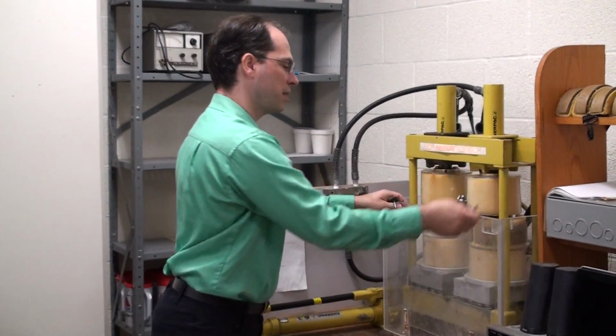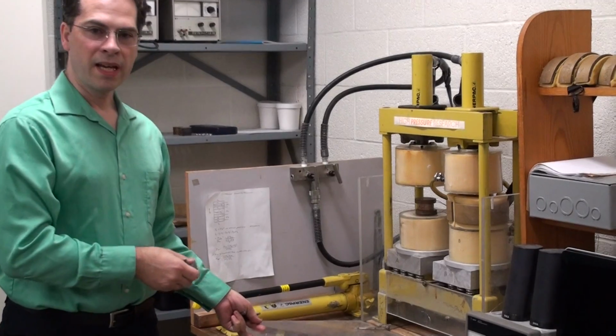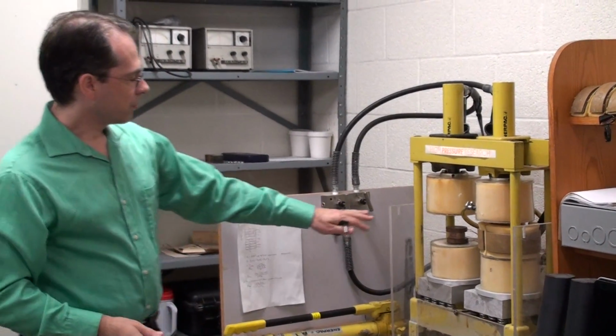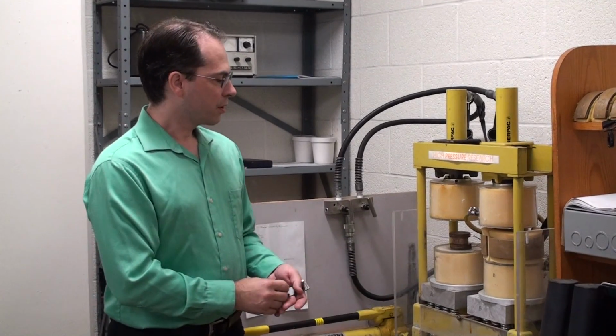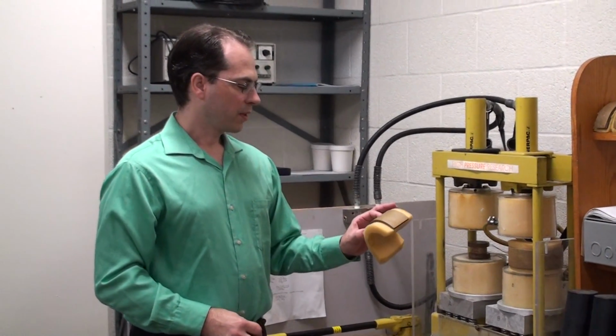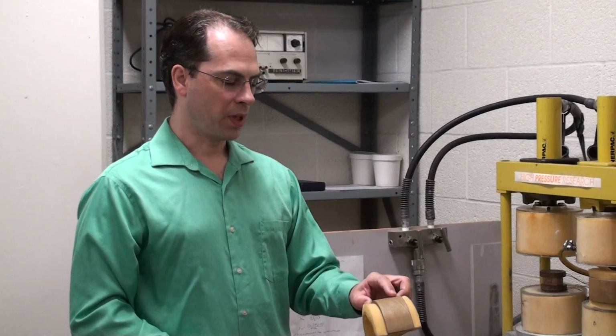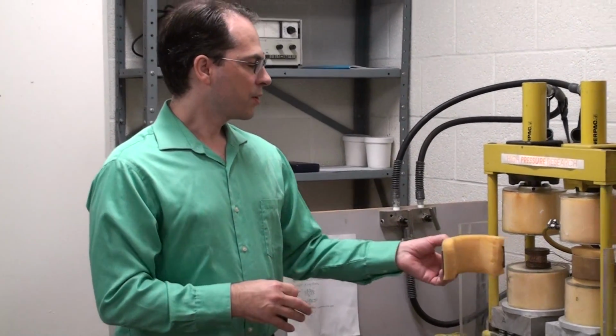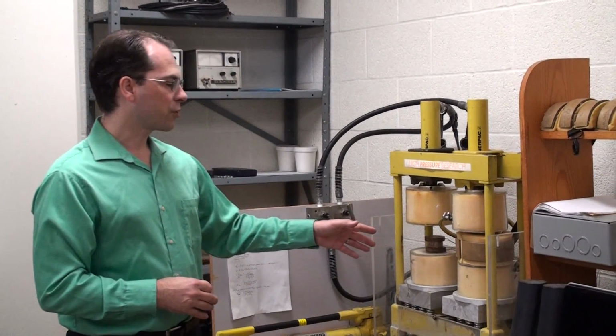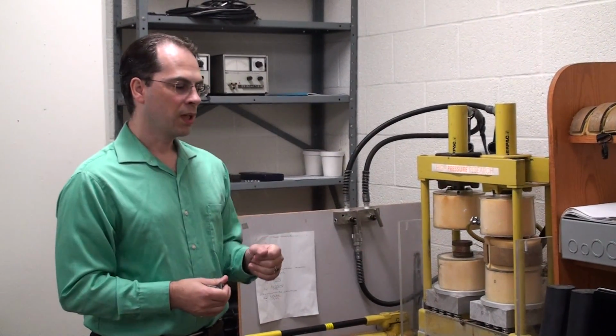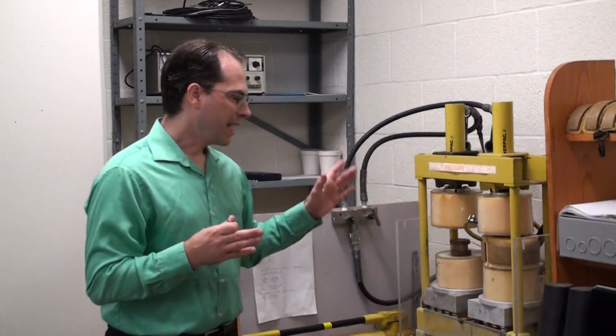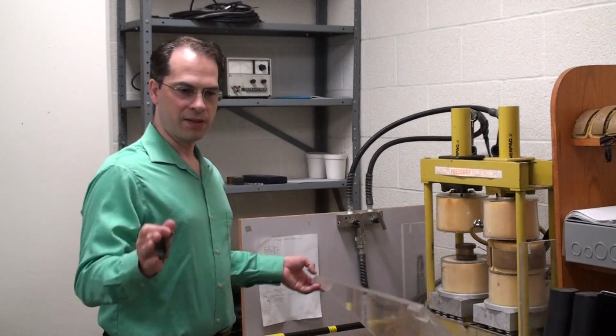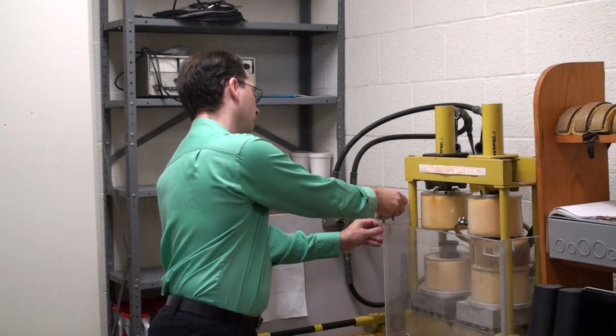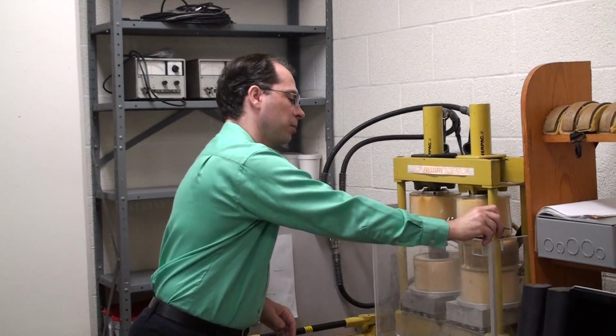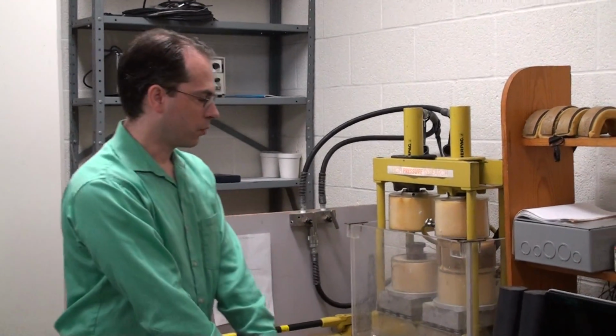You can see here, this is 1/2 inch thick hockey glass, shatterproof, so that when samples are put in, first they get surrounded by these insulators, which are supported by resin impregnated cardboard, so that as a sample is pressurized, if the sample explodes, it'll be contained within those. If anything, which has never happened, got past those, it won't be able to get past the shatterproof glass, and a student sitting here working on the computer will be safe.